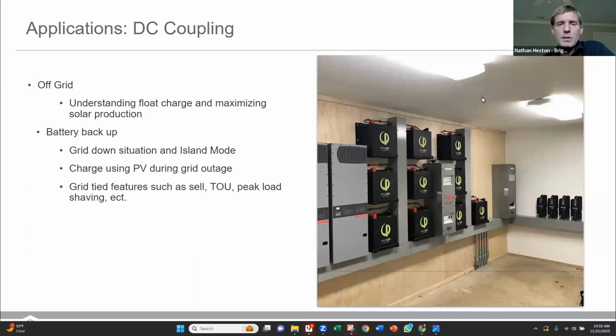In a DC coupled system, you run a charge cycle. Anytime you're using batteries, you're running a charge cycle. That charge cycle consists of 3 parts: a bulk cycle, where we push constant current into the batteries. Our batteries are rated at C/2. So if you have, for example, a 75 amp hour battery, you're going to be charging that at half that rate, 37.5 amps. You'll charge at a constant current until you reach the bulk voltage, which in our case is 56.0 volts. Then it goes into an absorb cycle where you hold 56 volts for 6 minutes, and then we'll float those batteries at 54 volts if excess solar is available, while that excess solar is being used to power loads.